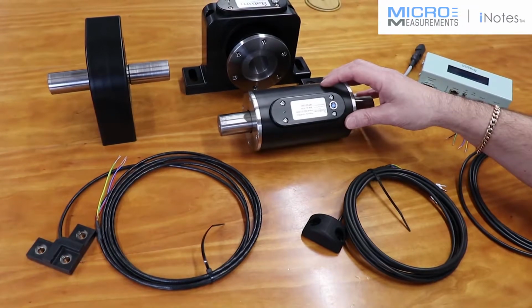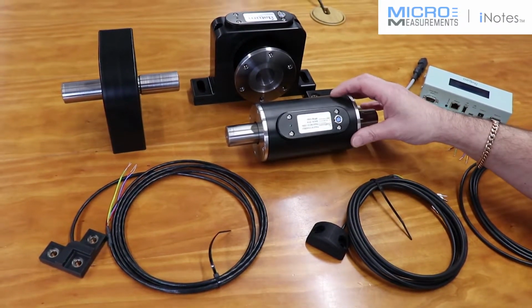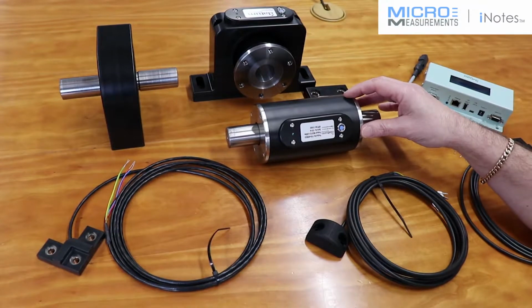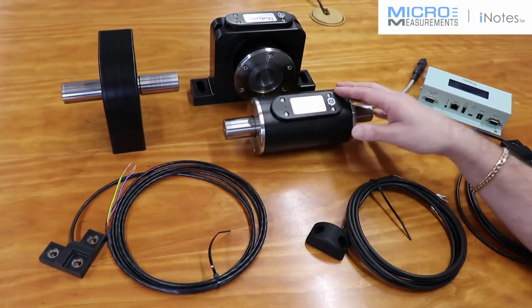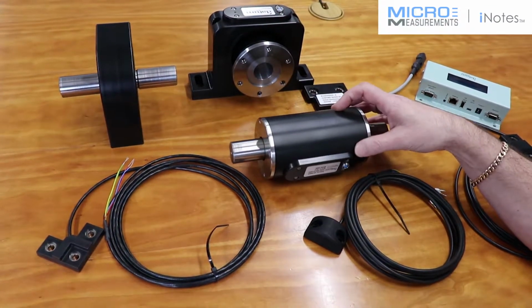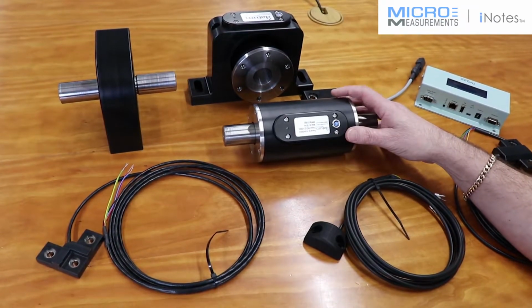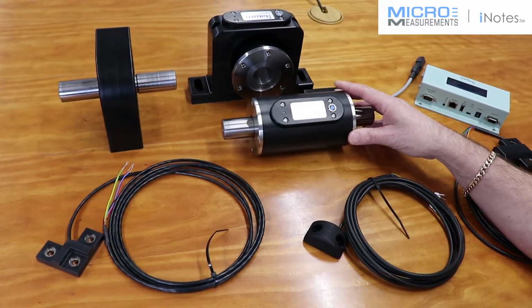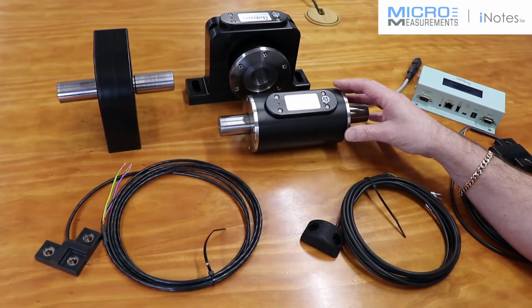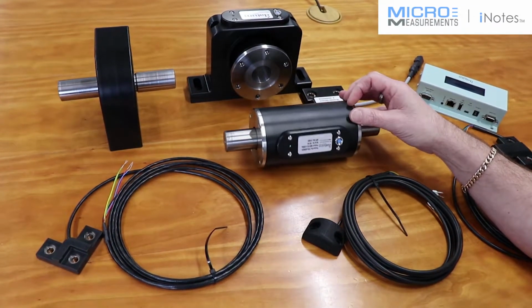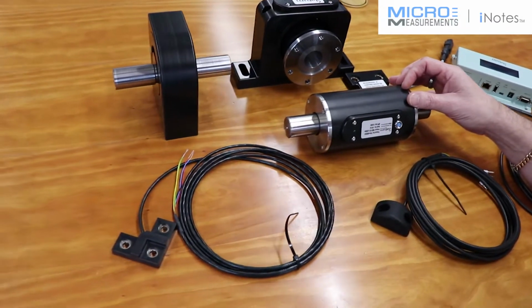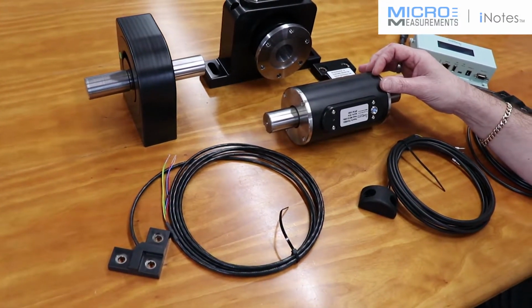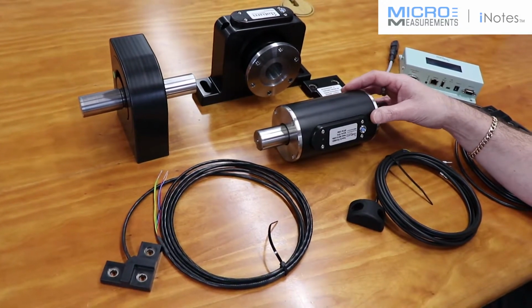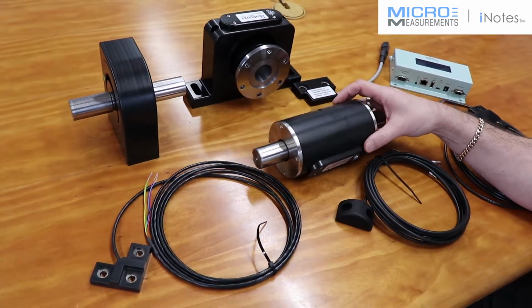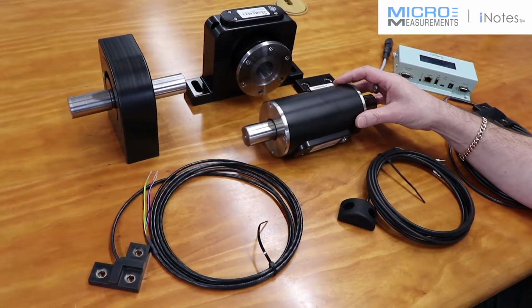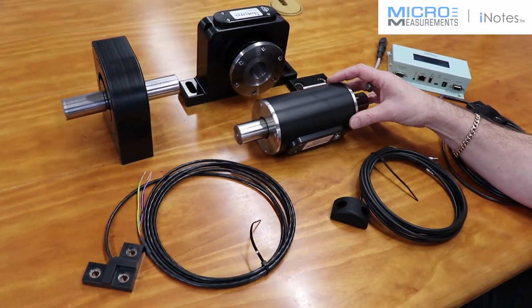We use Micro-Measurements gauges throughout all our transducer products simply because they're very reliable, the guys know what they're doing, it's a great product, and we get all the expertise and advice we need when we need it. The strain gauge follows exactly what the transducer is doing, so you get high accuracy, very good thermal response, very repeatable, and very reliable for long-term applications. They'll last 30 or 40 years without any intervention.